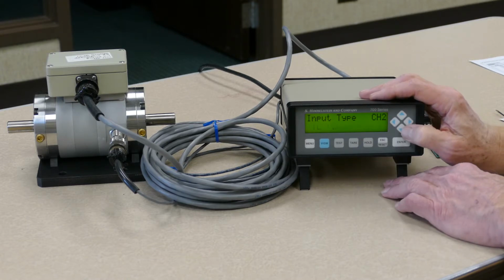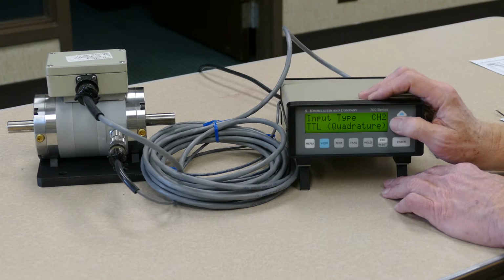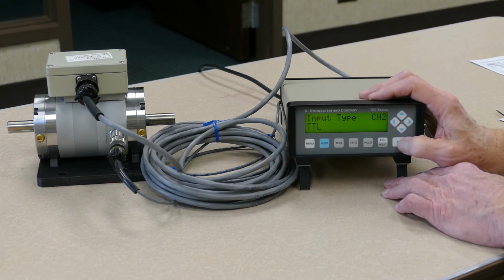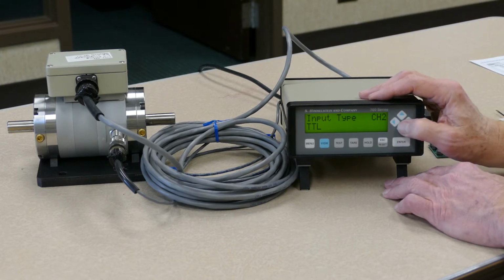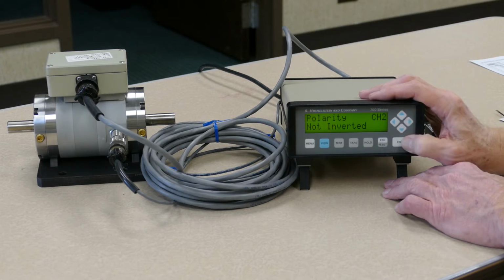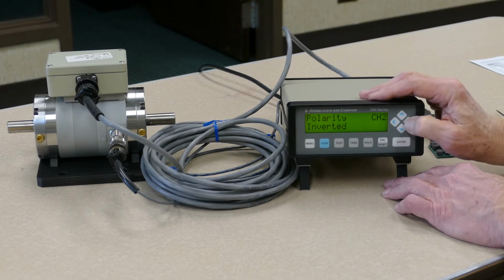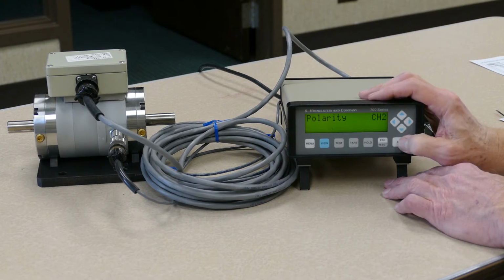Alternatively, with the right pickup installed, we can also accept a TTL quadrature style input, so you'll be able to get both speed as well as direction of rotation. But in this case, we'll go back and select TTL as the TTL input, press enter, accept that input, and then press the right arrow again. It asks you to specify the polarity, which is either inverted or not inverted. We leave that selection at not inverted. And then we can also select an input filter that would be applied to that signal. Typically we would leave it unfiltered, or you can select a 20 kilohertz filter on that input. So we'll leave that as unfiltered.